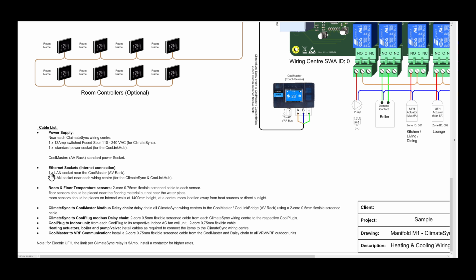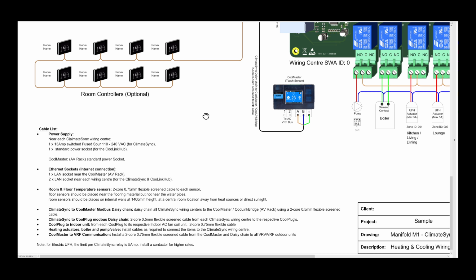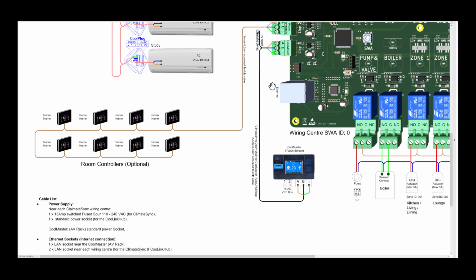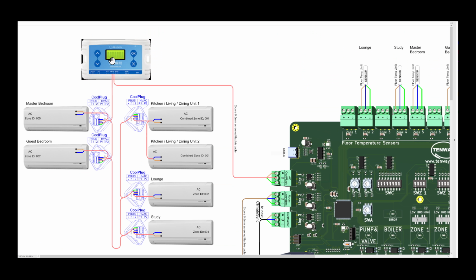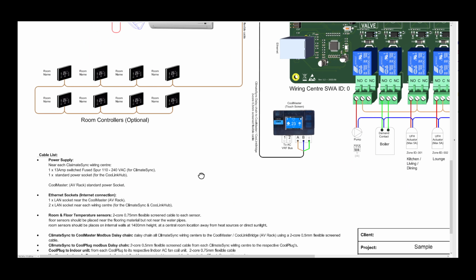We need one connection to the local internet connection. So one connection to the local switch for the CoolMaster, and 2 connections near the wiring center. One will go for the wiring center itself, which will connect over here, and another Ethernet connection to the CoolLinkHub. That will allow diagnostics and fault finding and some other features.